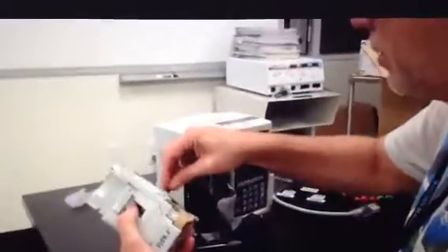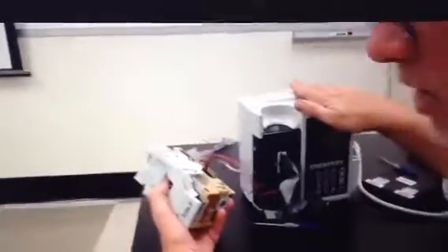So the first thing you do is you plug the power cable from the mechanism calibration fixture onto the pump. And you do that before you plug in the mechanism calibration device. Otherwise, you blow its power supply. Then you connect the data cable to the side of the mechanism and make sure it's properly seated on the mechanism calibration device.